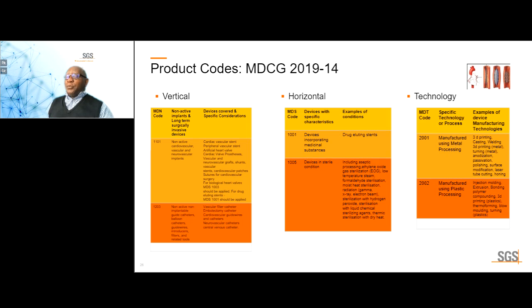At this point, I want to segue a little bit to another item that manufacturers need to take on board. Under the MDR, the requirement for competence is significantly higher and much more explicit. Manufacturers should also be aware of this. And the guidance document that will help you make this determination as it relates to your device is MDCG 2019-14. And typically, these codes fall into 3 buckets: the vertical, which relates to the product; then horizontal, which could be applicable to that type of product; and the technology, which is very specific as to the technology required to make the device.